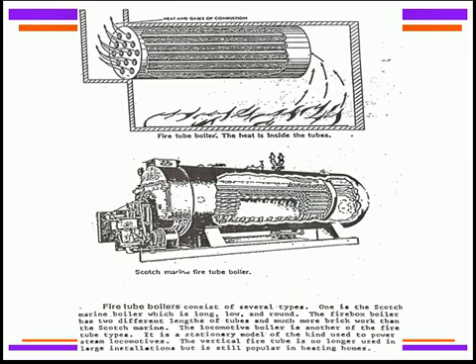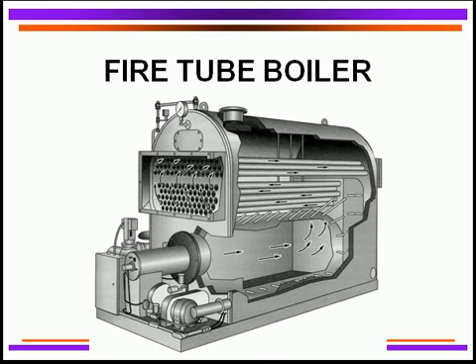The different types of boilers we have are, first of all, fire tube boilers. These are the ones that have been used for years and we still utilize them. This diagram gives a better understanding of the fire tube boiler — the flame actually goes to the back of the boiler and comes through the tubes. That's why we call it the fire tube boiler. The water is on the outside and it produces our steam.